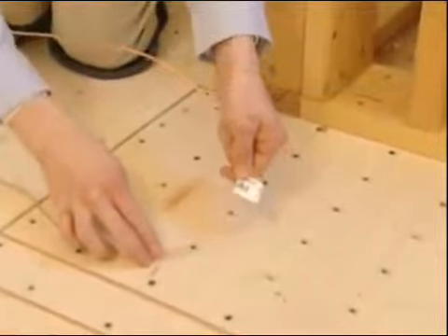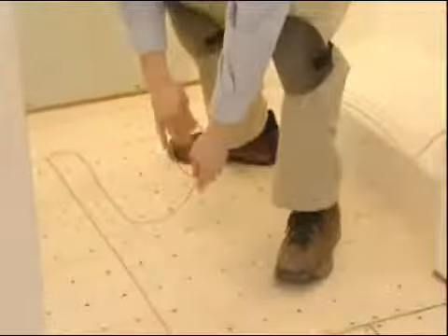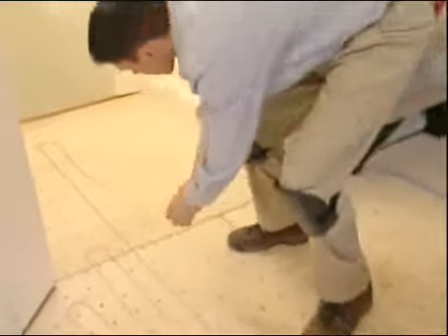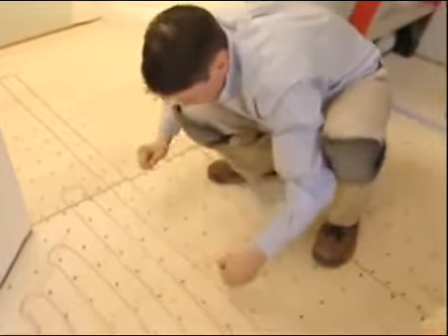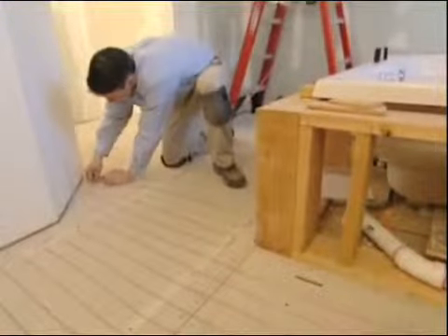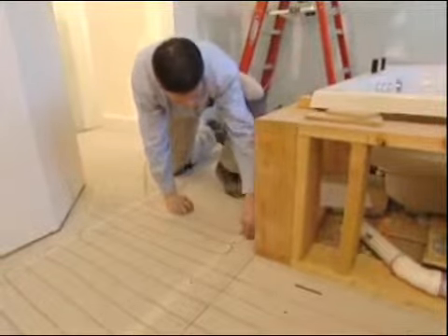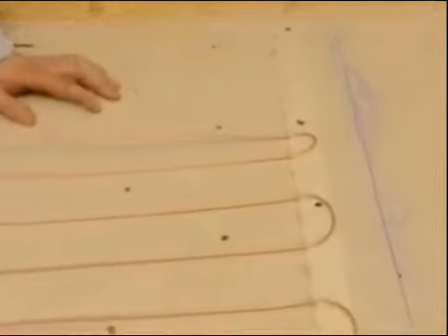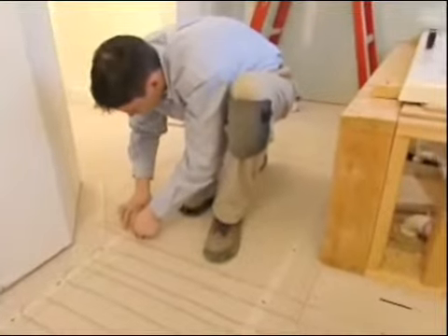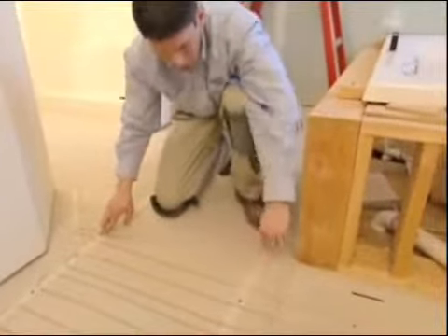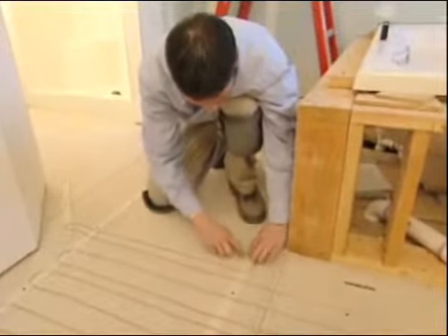Compare the location of the label to the corresponding 1/4 or half point previously marked on the floor. If the label has not reached the location marked on the floor, leave the low traffic area unheated. If the label has passed the mark, carefully lift the previous few cable runs and place in a 1½ inch spaced run between the 3-inch runs to use up the excess cable. No less than 3 standard intervals of cable spacing should separate these additional 1½ inch intervals.